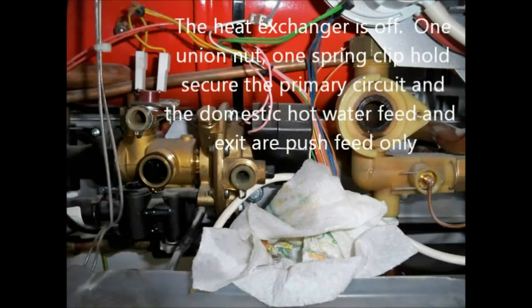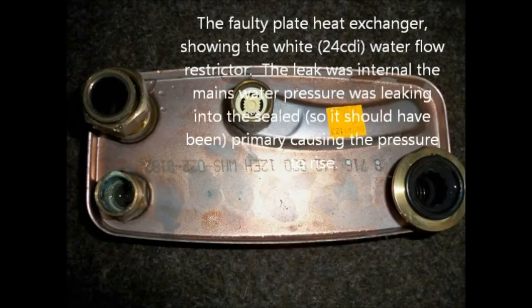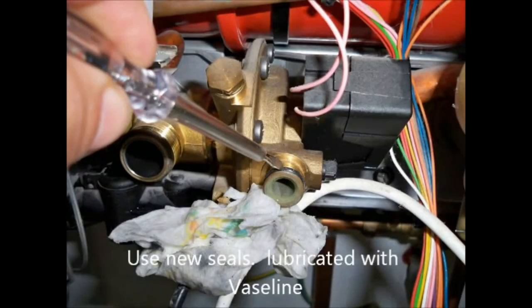The heat exchanger is off. One union nut, one spring clip holds secure the primary circuit, and the domestic hot water feed and exit are push fit only. The faulty plate heat exchanger showing the white 24 CDi water flow restrictor. The leak was internal. The mains water pressure was leaking into the sealed, so it should have been, primary, causing the over pressure. Use new seals, lubricated with Vaseline.